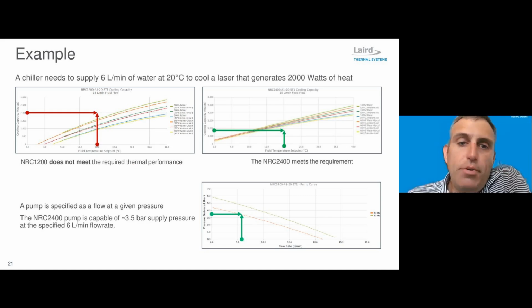So let's take a quick example of a chiller that's needed to provide 6 liters per minute of water at 20 degrees C to cool a laser that's generating 2,000 watts. Looking at the NRC 1200 performance curve in the upper left-hand corner of this slide, we start with the cooling capacity on the y-axis and go across until we meet the fluid temperature set point. You can see that this performance point is above the capacity of the 1200. So that doesn't meet the performance, and we need to go to the next size larger model.